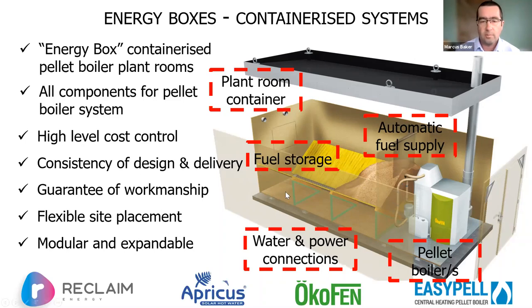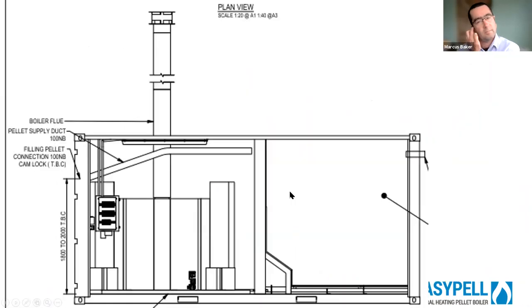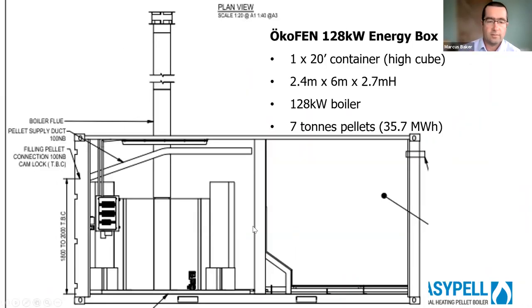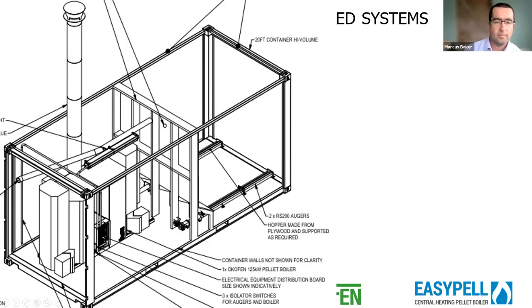Workmanship, and flexible site placement is obvious with a container. It's a lot easier to move water and power around than anything else. And they're also modular and expandable. So if we just have a look at these modules. Here's an example of a 128 kilowatt energy box in a single 20 foot high cube container. So for those not familiar, that's 2.4 meters wide, 6 long, 2.7 tall. And we've got a boiler and then about 7 ton of pellet store on this side. So it's an isometric view. And you can see you've got double auger.